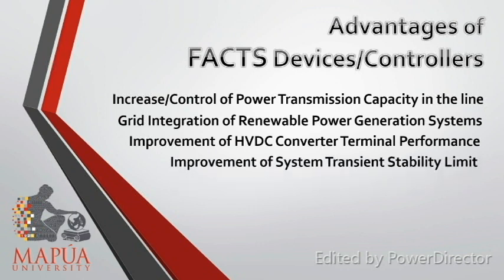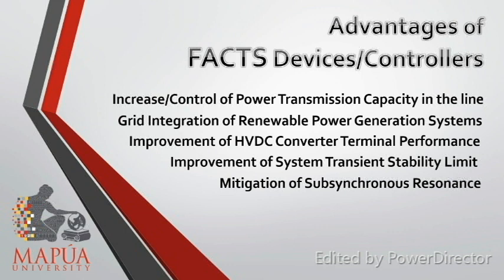Improvement of the system transient stability limit by controlled shunt compensation is achieved by increasing the power transmission via increasing or maintaining the transmission line voltage at the midpoint during the accelerating swing of the disturbed machines. FACTS help in the mitigation of subsynchronous resonance because this kind of resonance occurs at less than 60 Hz, which historically damaged the shaft of generators. It is also used for limiting short-circuit currents by rapidly changing from a controlled capacitive to inductive impedance.